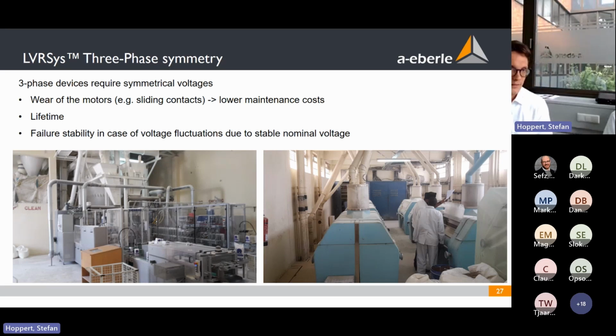So in the end, we solved the problem with our system. The customer said they have far less maintenance costs. They have not a lot of stops in the production, and the motors are working quite fine. The lifetime of all the equipment is going higher, and the stability due to the stable voltage is far higher, because you can imagine if the voltage is too low and you regulate it to a higher level, even if it's a short dip or it's going down a bit, it's still on a higher level, that it's constant and stable and supplies you for a longer time.